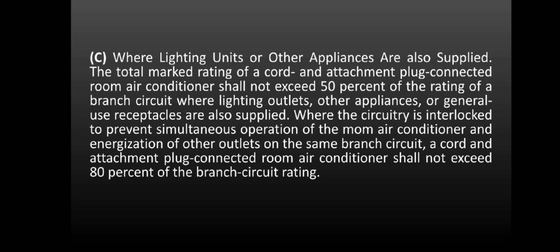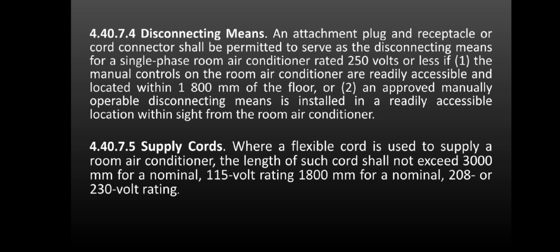Disconnecting means. An attachment plug and receptacle or cord connector shall be permitted to serve as the disconnecting means for a single-phase room air conditioner rated 250 volts or less if the manual controls on the room air conditioner are readily accessible and located within 1 800 mm of the floor, or an approved manually operated disconnecting means is installed in a readily accessible location within sight from the room air conditioner.